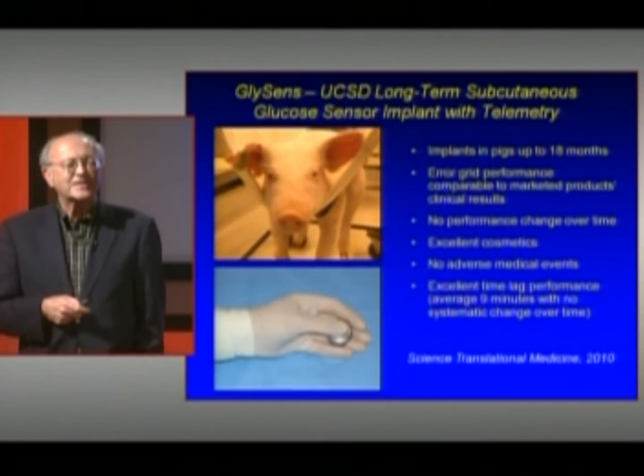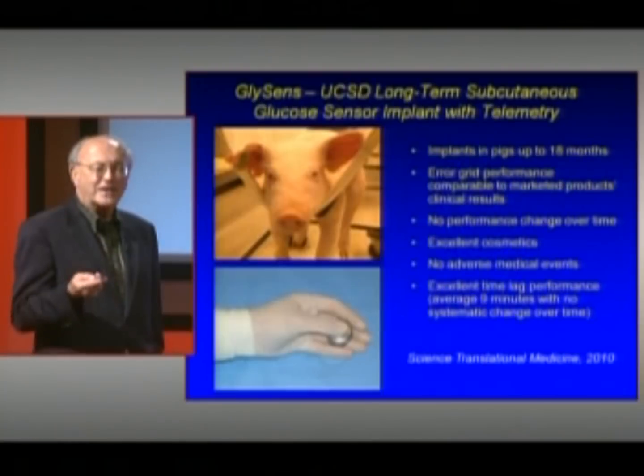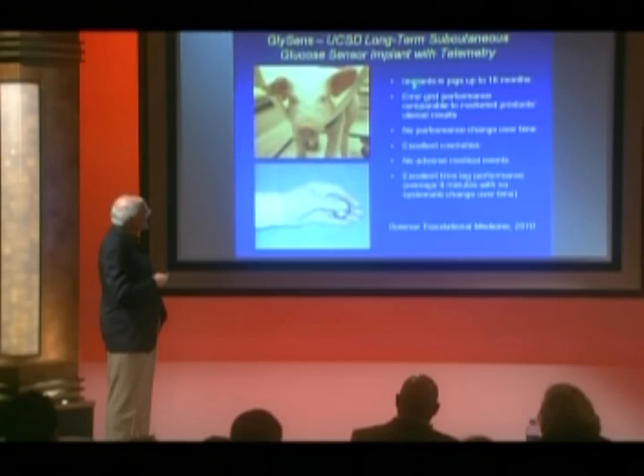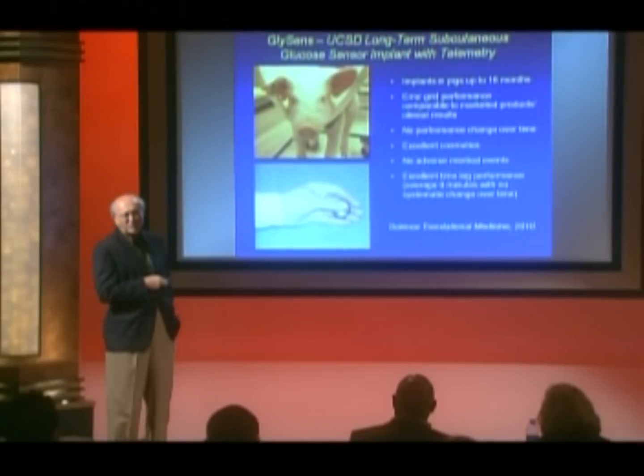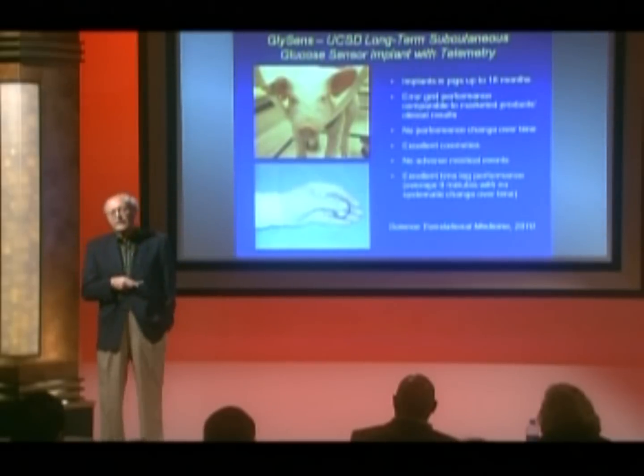Much has been said in praise of the pig today, and I want to continue with that. I'm going to tell you about the GlySens UCSD long-term subcutaneous implanted glucose sensor with telemetry. These are the experimental animals we use, and this gives you an image of the sensor implanted in the animal to show its size. We've implanted these devices in pigs for up to 18 months, working continuously. Their performance is comparable to sensors presently used in clinics that are percutaneous. There's no change in performance over time, no adverse medical effects, and a lag of about nine minutes, well within the time needed to accurately follow blood glucose.